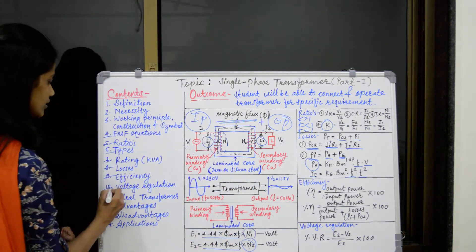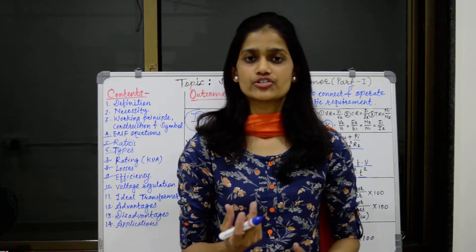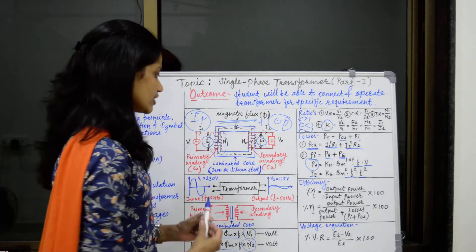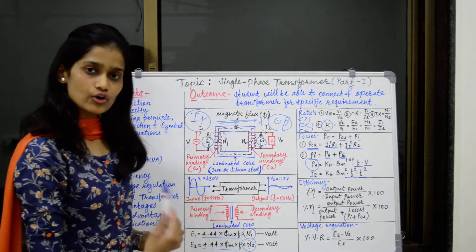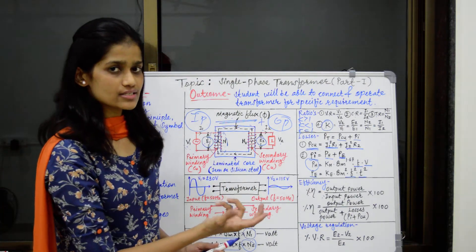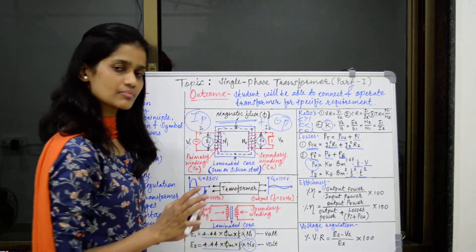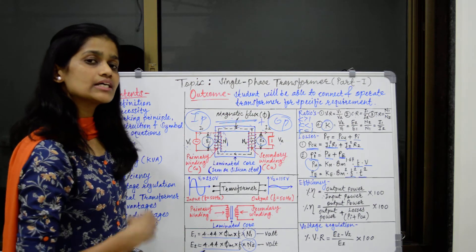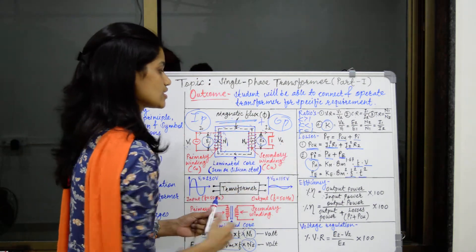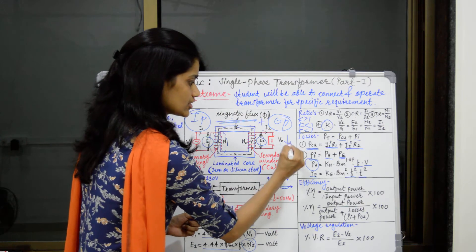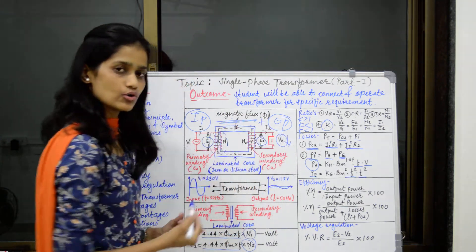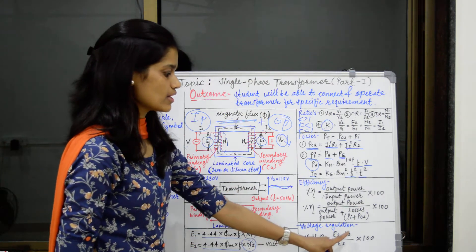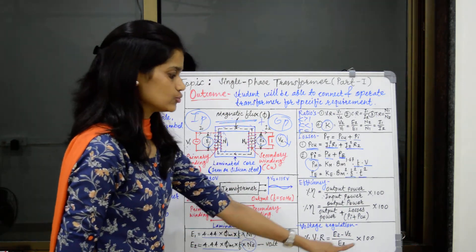Next is voltage regulation. Regulation means change. Ideally, when we increase the load of the transformer, the load current increases but the secondary terminal voltage must remain constant. But practically, when we increase the load, current increases and there is a small decrease — a small change — in the secondary terminal voltage. This is nothing but voltage regulation, and it is found as: (E2 − V2) / E2 × 100.